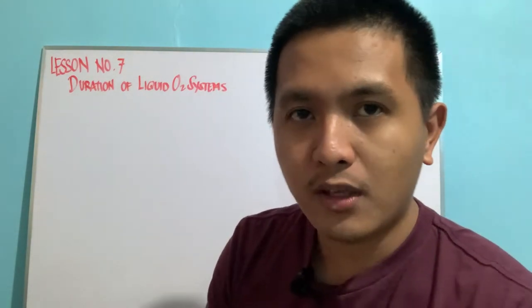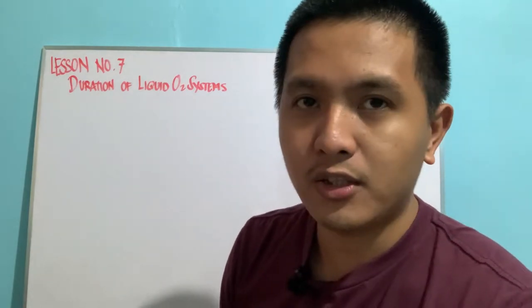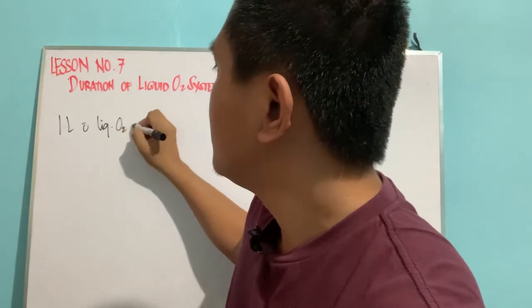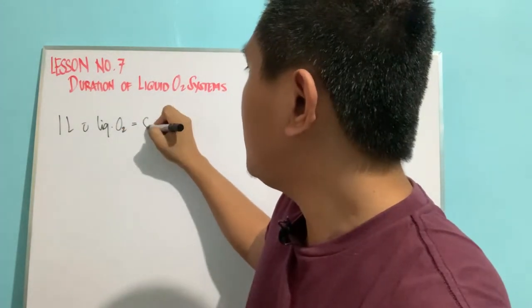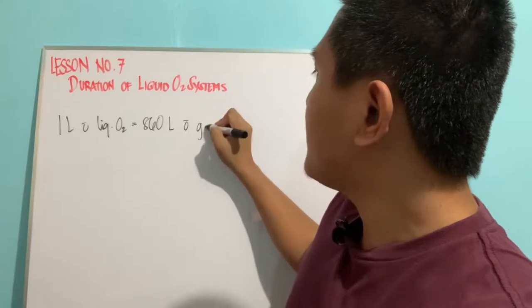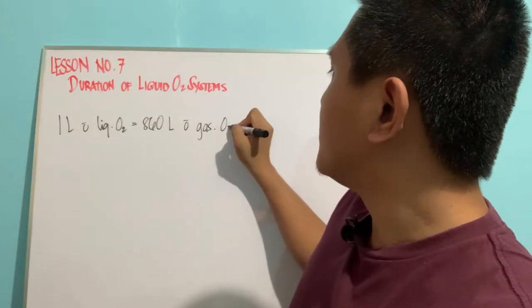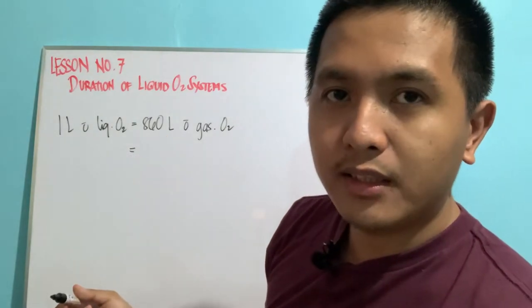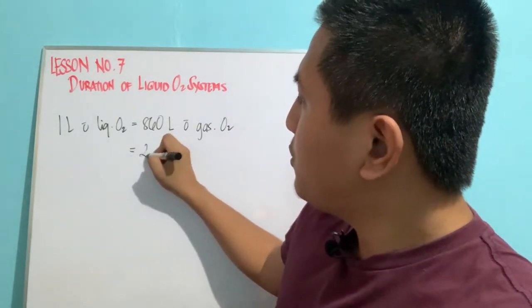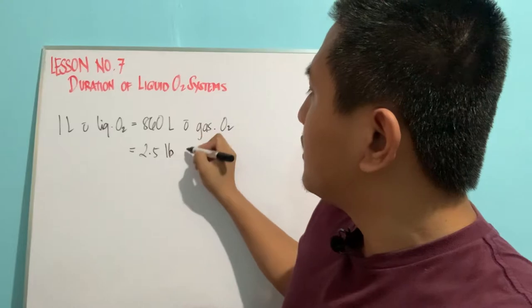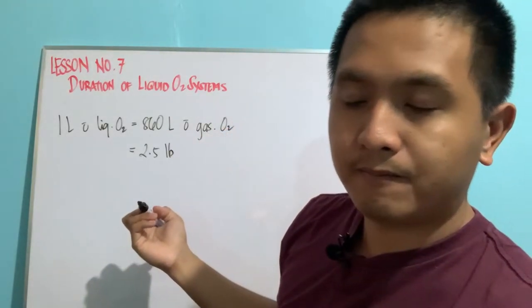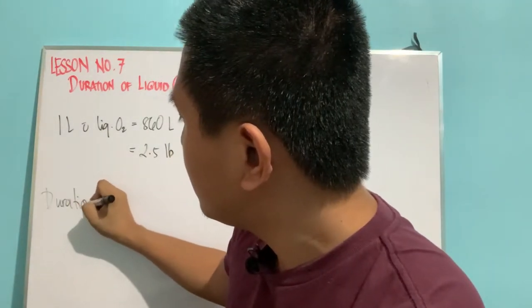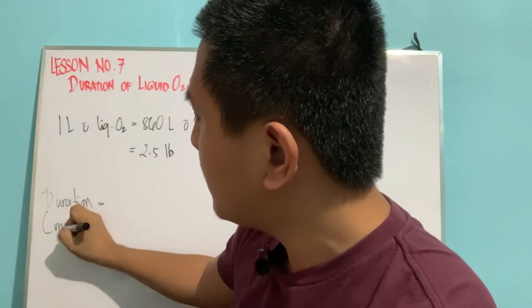Some things to remember when dealing with liquid oxygen system calculations: one liter of liquid oxygen is equal to 860 liters of gaseous oxygen. Remember also that one liter of liquid oxygen is equal to 2.5 pounds of gaseous oxygen.